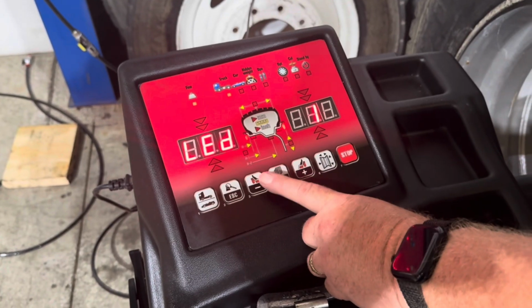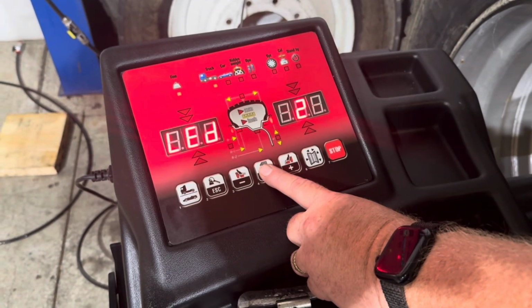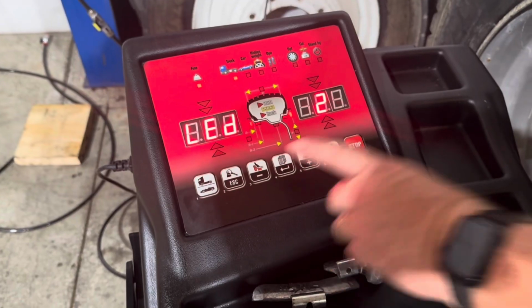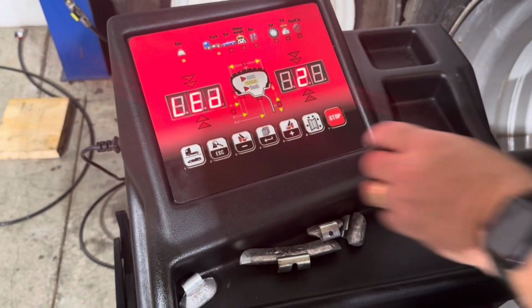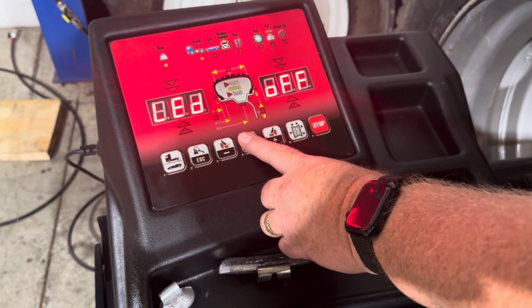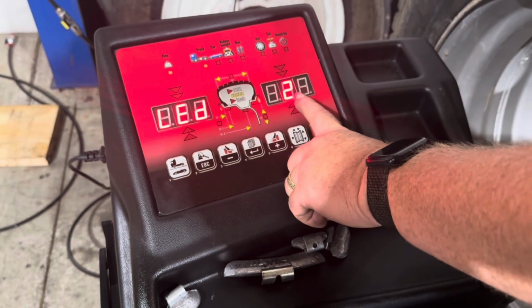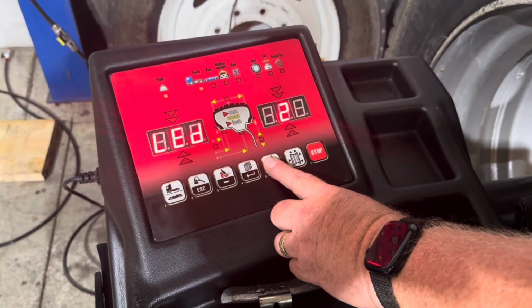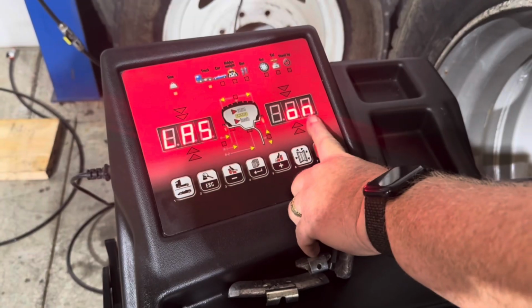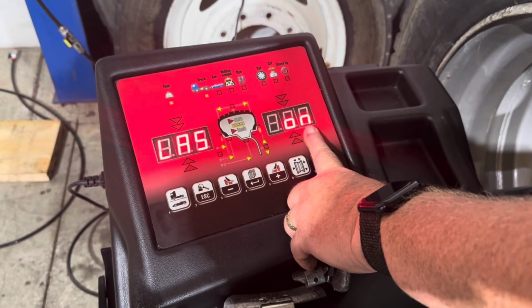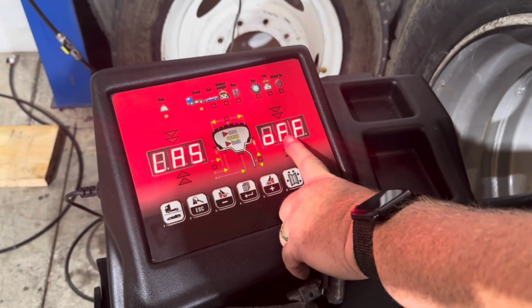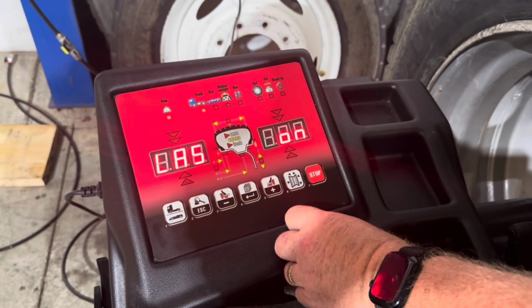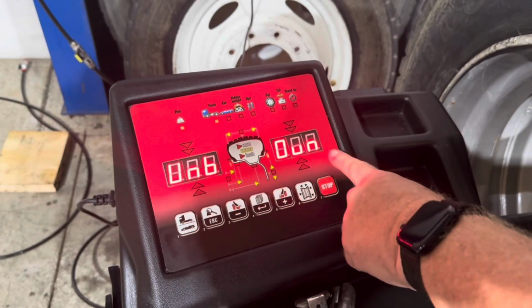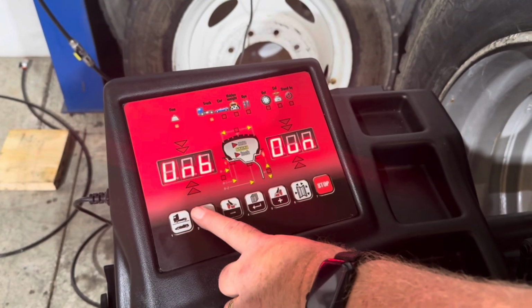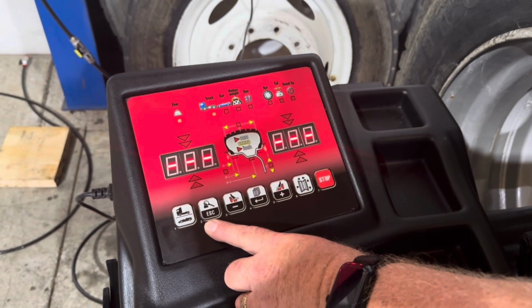LED is the brightness of the LED light. We can turn it on 1 or 2, or that's the light for the inside of the wheel, or we can turn it off. Typically in a dark environment, we want to leave that on 2. Laser on or off. If you're using the laser mode, you'll want that on. If it's off, simply turn it on. We're back to our unbalanced ounces. We're done with the setup mode. We can get out of that.